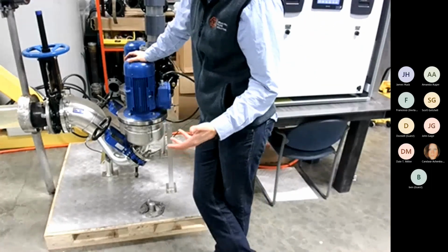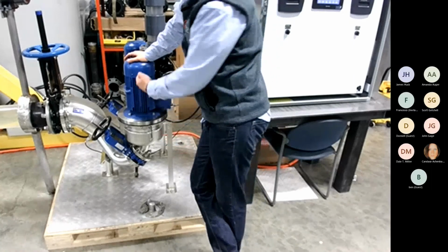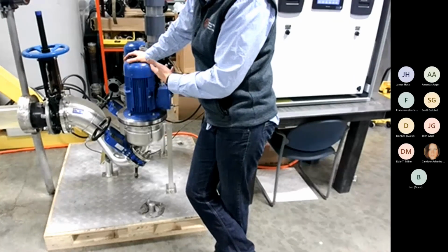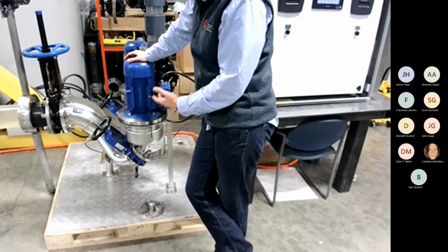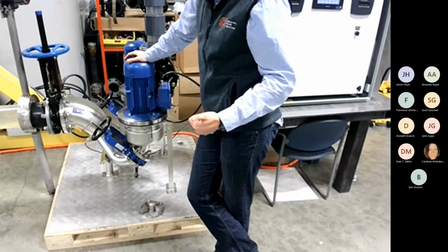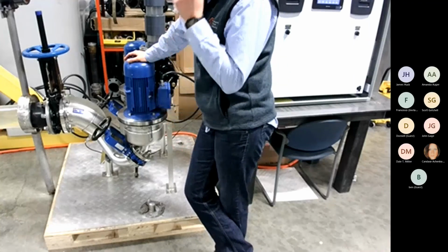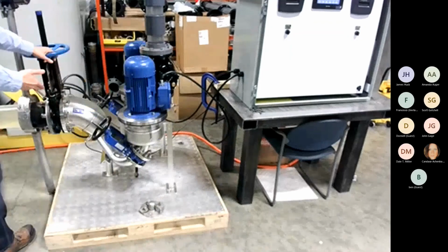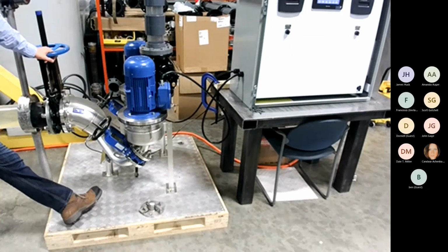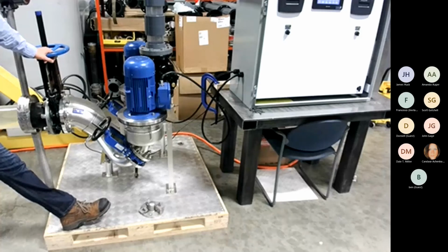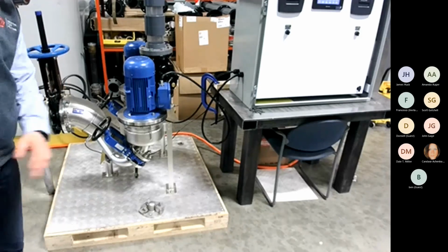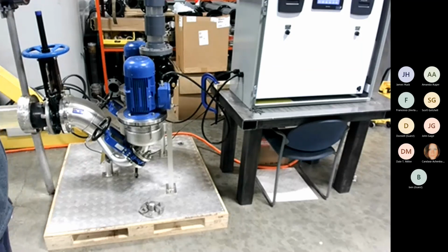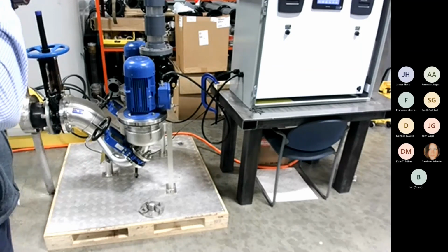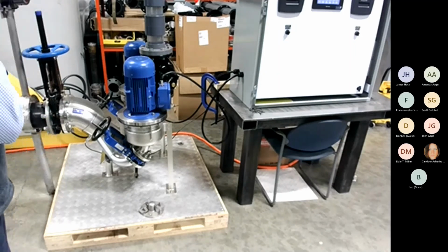If you wanted to have spare parts, I would probably recommend a spare motor. The motor should last a very long time, but if it goes down, you're going to need one. Mechanical seals fail over time in all pumps, so a mechanical seal would be good to have. The pressure transducer would probably also be something to have on the shelf. If you have a sandy, gritty environment that would wear down an impeller over time, you'd probably want one for the long term, though it's not really a short term need. Other than that, there's not many items you need to maintain or keep on the shelf.